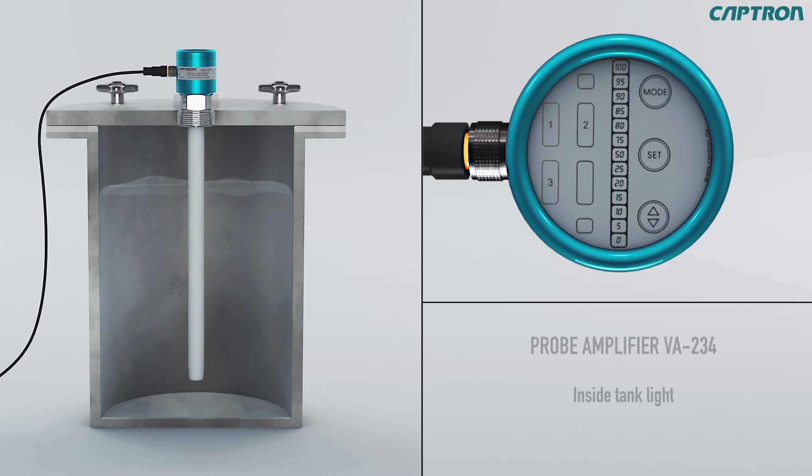Optionally, there is lighting available for the inside of the tank of the probe amplifier VA234. To turn on the LEDs, just touch the set button in measuring mode. The lighting shuts off automatically after 15 seconds to avoid overheating, and can be turned on again after waiting 5 seconds.